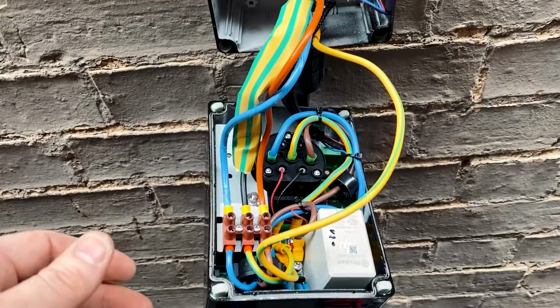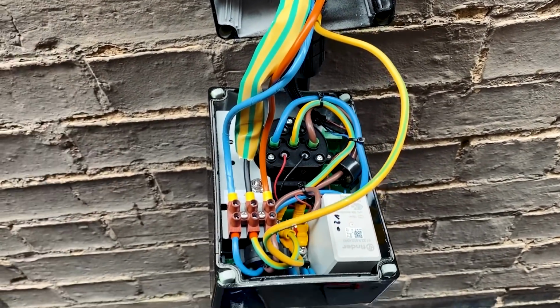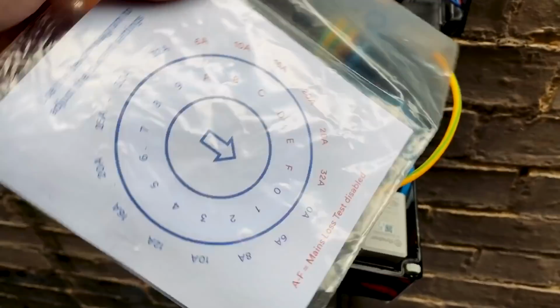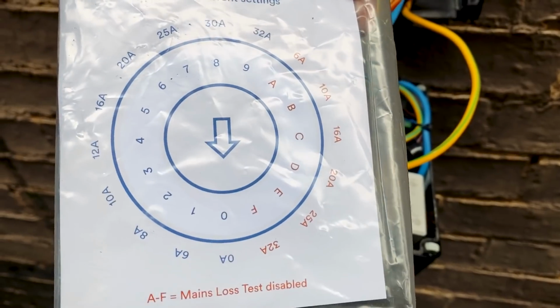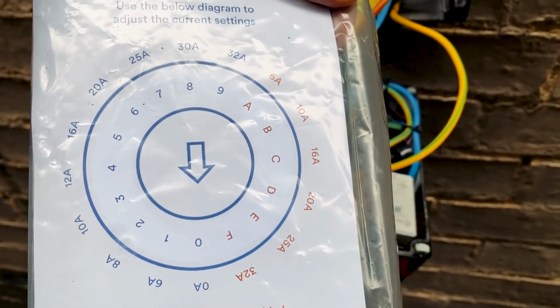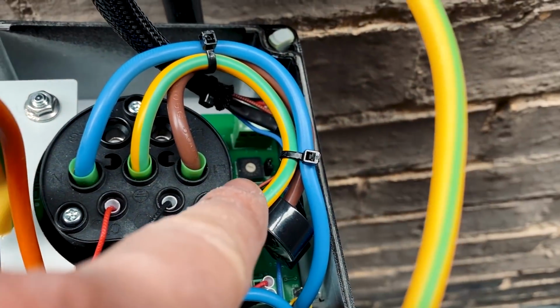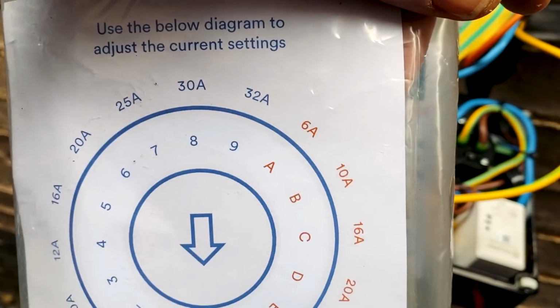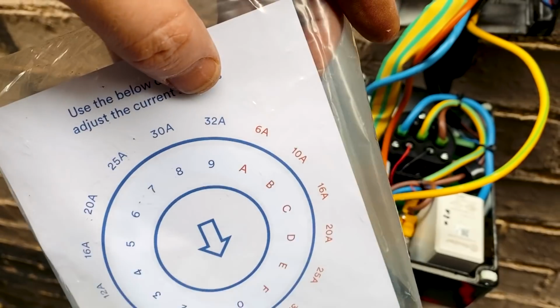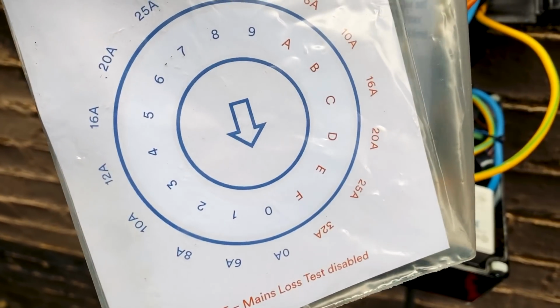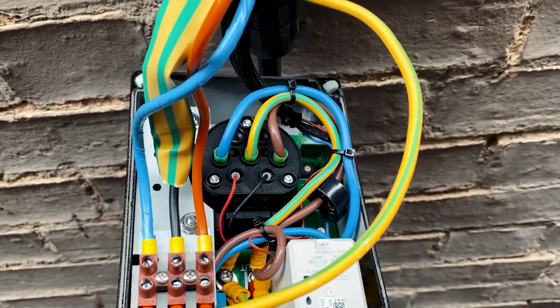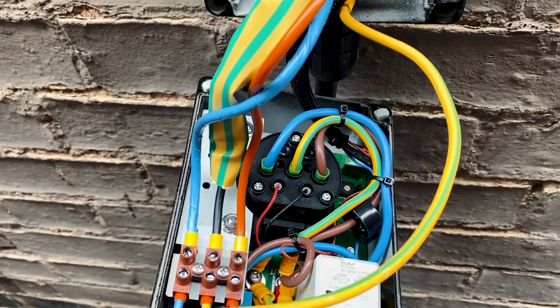I'm going to go and connect it up at the other end and then start doing some tests. There's a couple of really important things the instructions require before commissioning these. One is this chart, which shows that by default the charger is set to 0 amps, so if you don't adjust this little dial it's not going to charge. You need to set it to the correct amperage setting - normally for a 7 kilowatt charge it'll be 32 amps, but in this case I've set it to number 5, which is 16 amps, just to limit it for the moment to avoid risking blowing the main fuse.